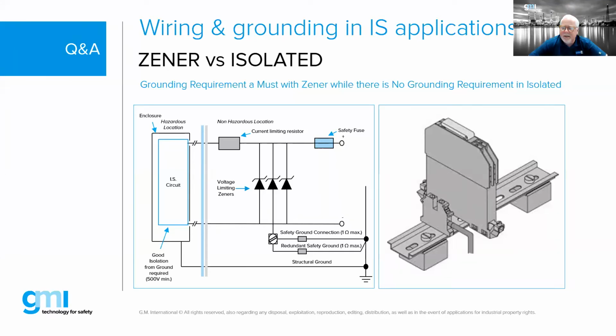Yeah, this is very common. The picture on the right-hand side shows an example of a Zener barrier, and one of the things people forget is that the Zener barrier is mounted to a DIN rail, and that DIN rail is part of the ground, if you will. So we want to make sure that when we're doing Zener barriers, if the DIN rail is attached to the enclosure itself, we use insulated standoffs to make sure that DIN rail is not actually in contact if we're using a metallic enclosure of some sort. That's typically what you would do for mounting Zener barrier type products, and you would not generally mount those on the same DIN rail as your other devices.